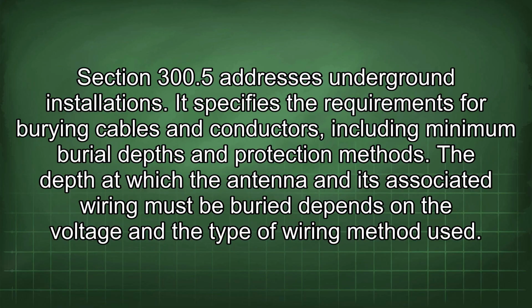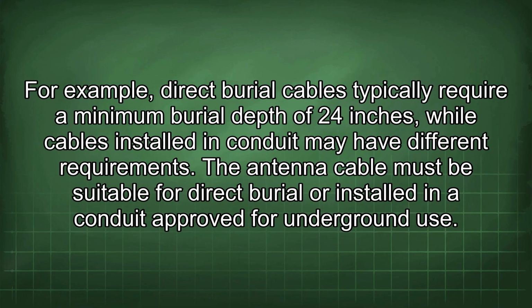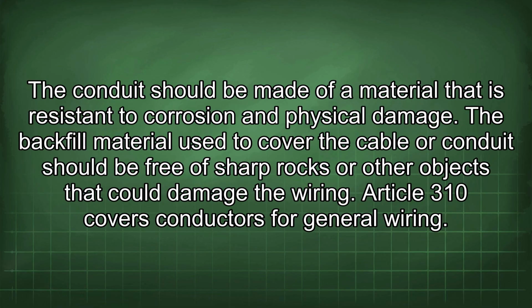The depth at which the antenna and its associated wiring must be buried depends on the voltage and the type of wiring method used. For example, direct burial cables typically require a minimum burial depth of 24 inches, while cables installed in conduit may have different requirements. The antenna cable must be suitable for direct burial or installed in a conduit approved for underground use. The conduit should be made of a material that is resistant to corrosion and physical damage. The backfill material used to cover the cable or conduit should be free of sharp rocks or other objects that could damage the wiring.